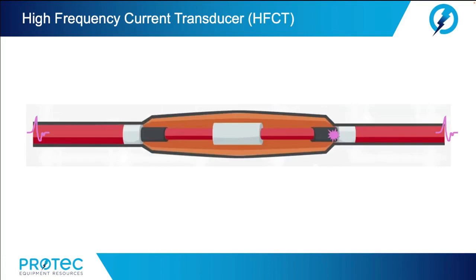The HFCT sensor has a split core, and so it simply clamps around a lower resistance grounding lead. HFCT sensors have a distinct advantage of being able to detect partial discharge signals on cables from long distances, up to a kilometer away. Now, this limit depends on the type of ground shield and the strength of the PD pulses. This means that multiple PD signals and noise signals can also be detected from many points on the ground grid where a grounding lead is exposed.